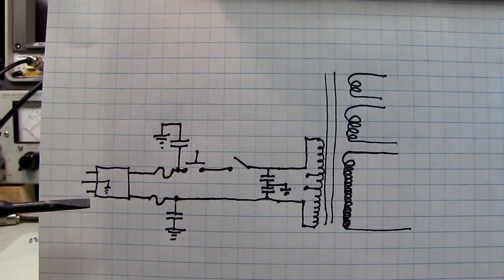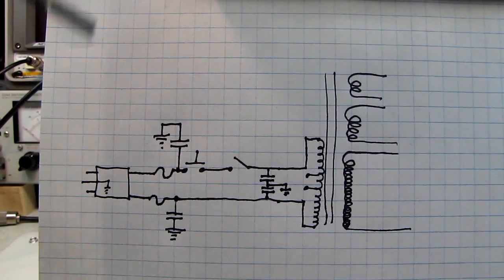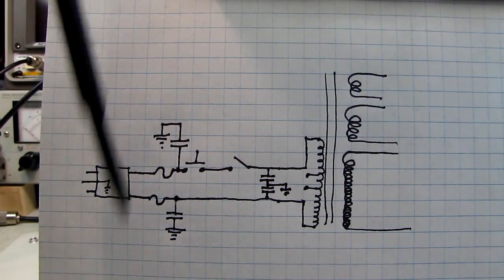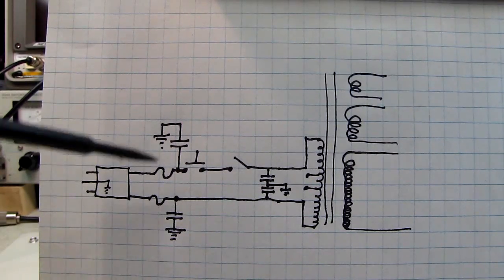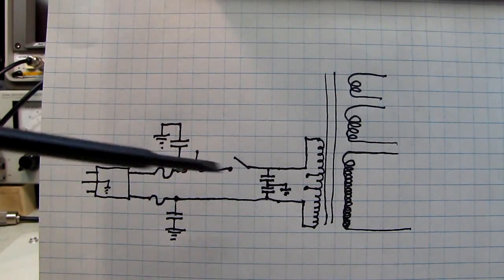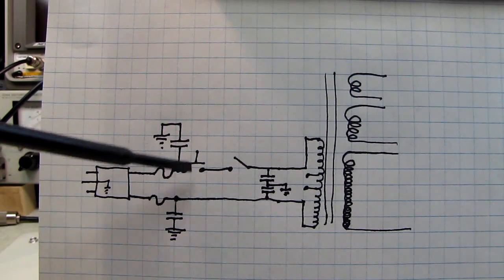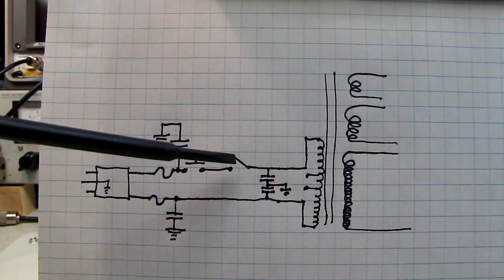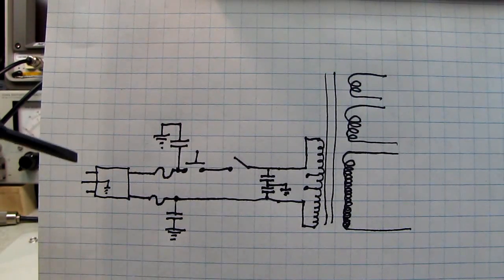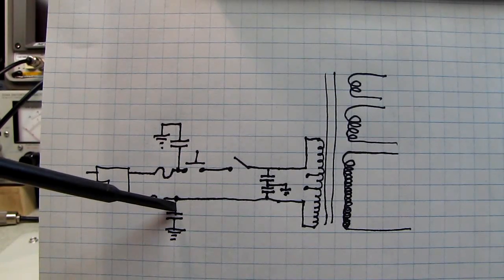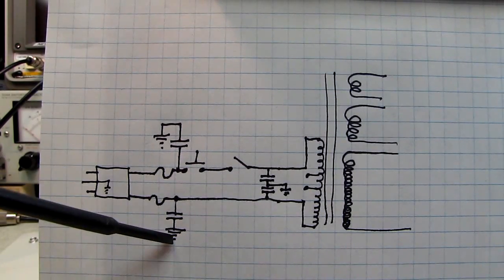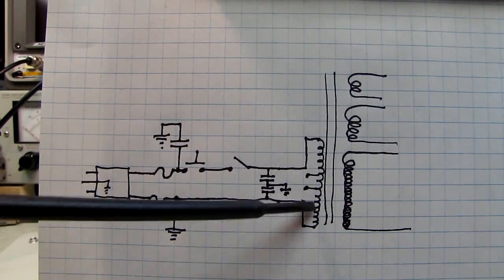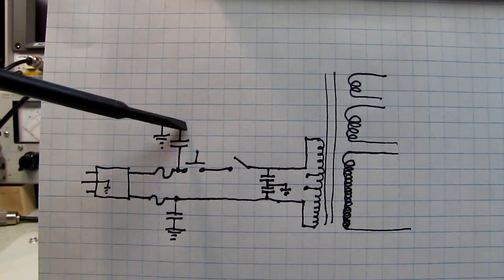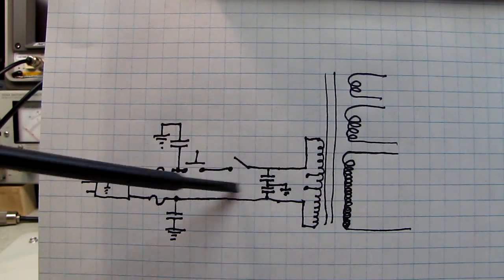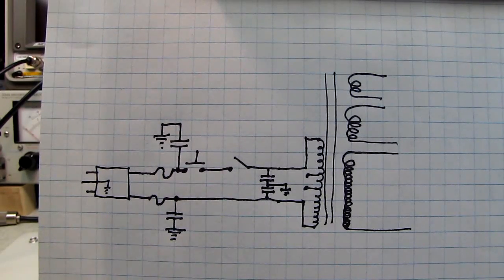We come in from the plug, there's 2 fuses, we have a couple of bypass capacitors. Now at first glance I quickly said, the bypass cap is gone, but there's no path to ground because both of these switches are open. This is the safety switch on the cover. This is the main power switch. If this capacitor was leaking to ground, there's no path for the current through the primary. If this capacitor is leaking to ground, again, because the switches are open, there's no path through the primary.